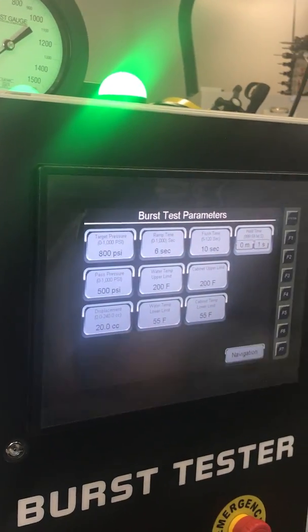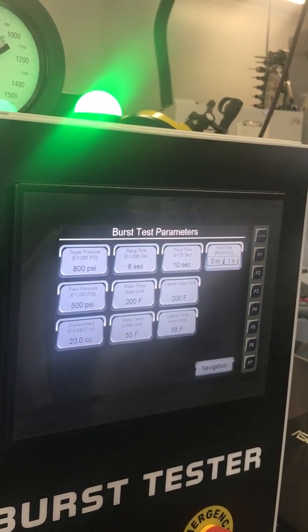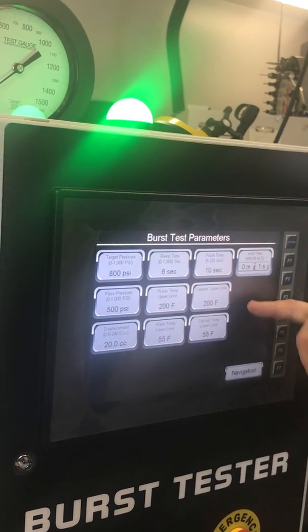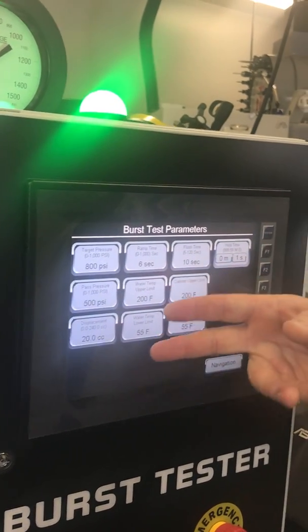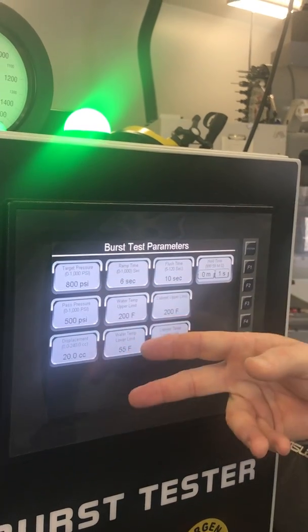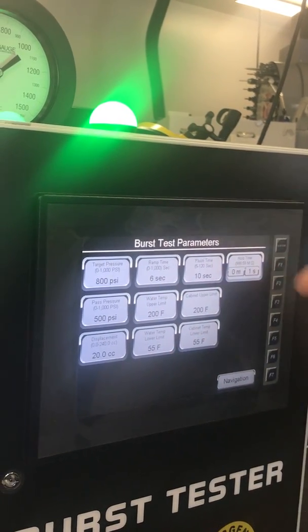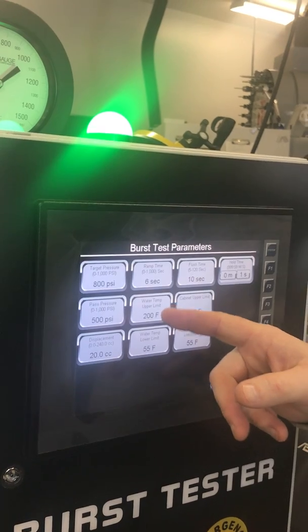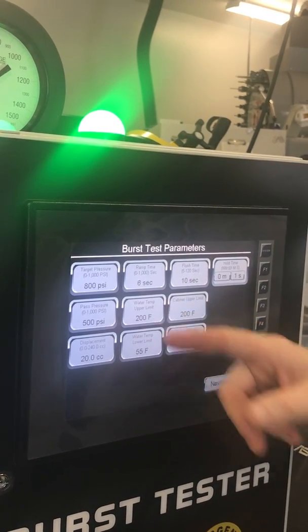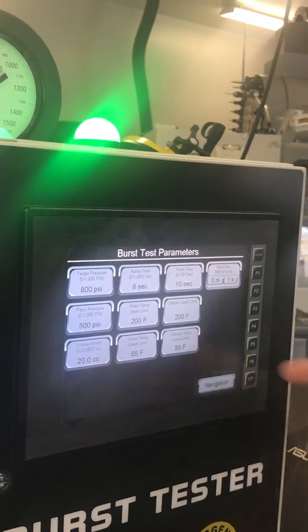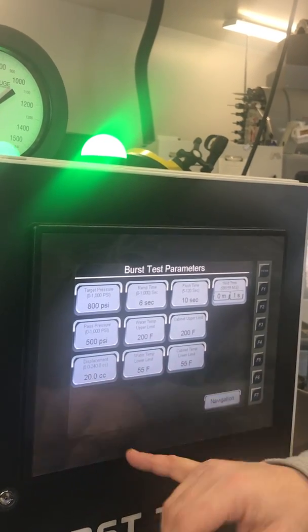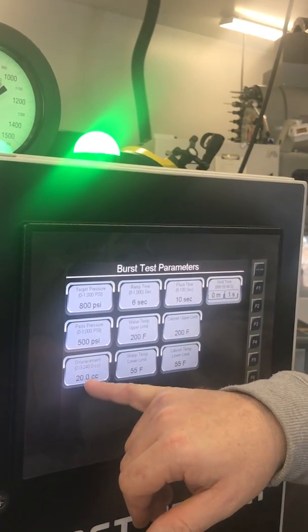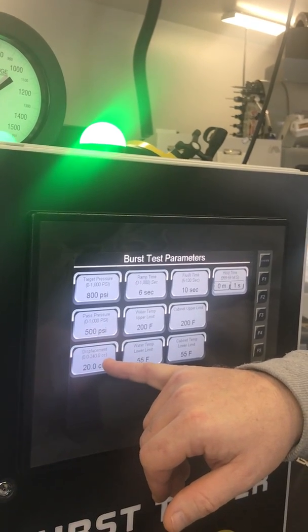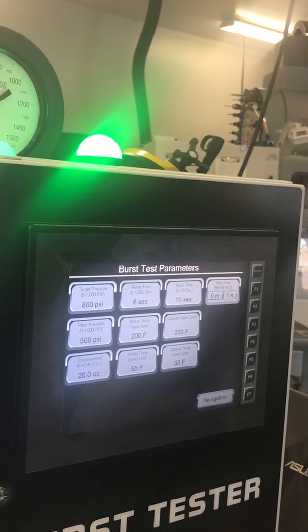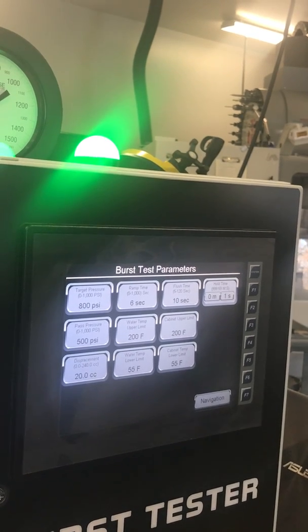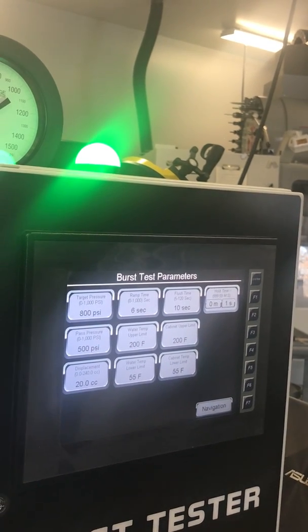I personally opened them up so I could run my testing. And then the cabinet alarm temp, same for that. And these are the same registers, the same set points from the static to the burst. So my point is, if you change them here, they're going to be changed. That's not true. Never mind, forget I said that. They're different registers. Displacement, if we ever exceed this amount, it's going to fail. You have a bad part. I've got it set at 20 cc's now, and you go 0 to full stroke is 240 cc's. Okay.